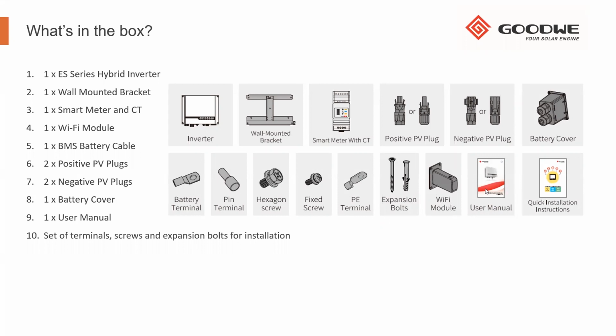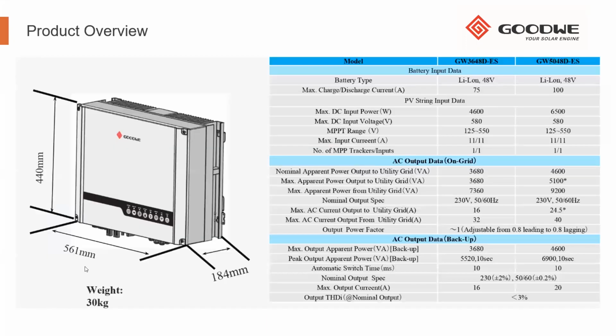In the box as well, you'll find the user manual and the quick installation guide. The quick installation guide contains a lot of installation guidance for our approved batteries. Just a brief overview, I think Warren went mostly through this. Most of the considerations you'll see are on the sides, below, and for the installation. I see there was a poll question regarding trunking below the inverter. Should the trunking not be right against the unit, it is fine. It is generally recommended to keep it a certain distance away so there's sufficient airflow for the bottom of the device.